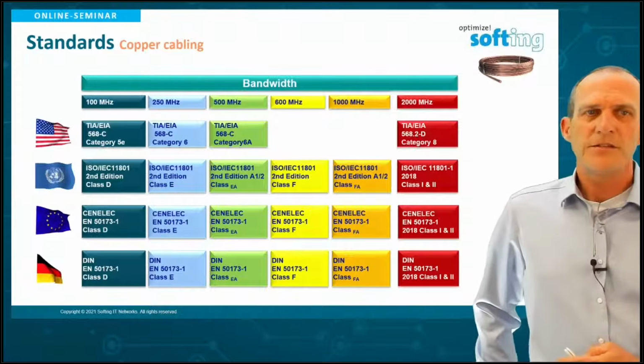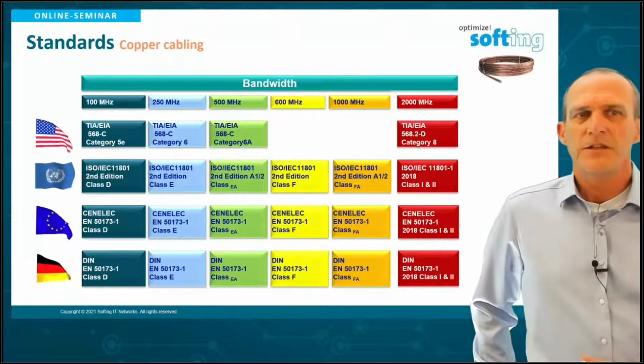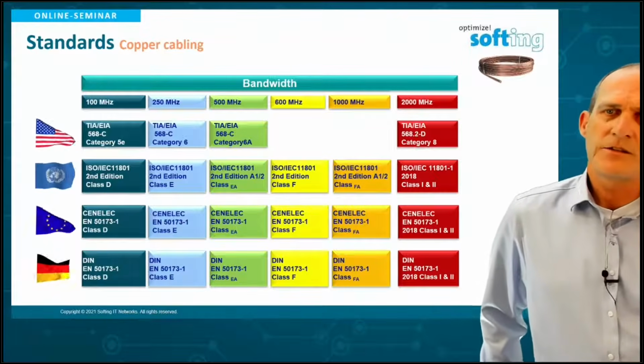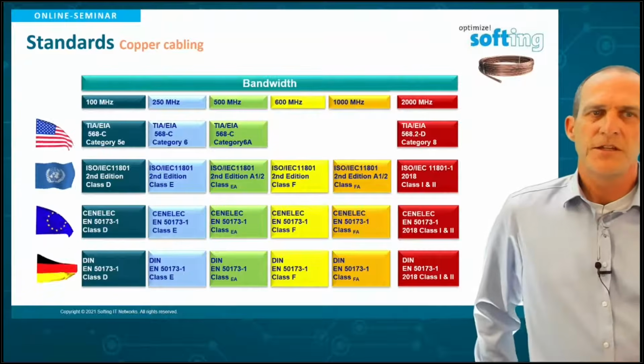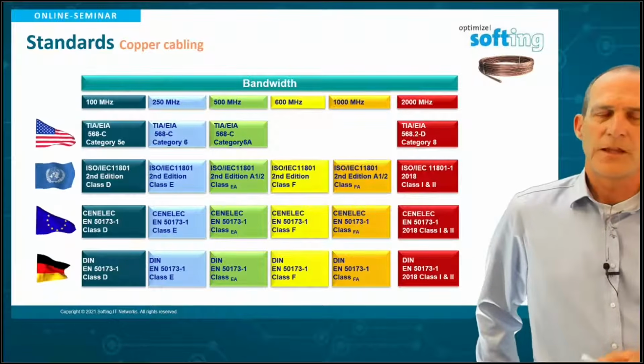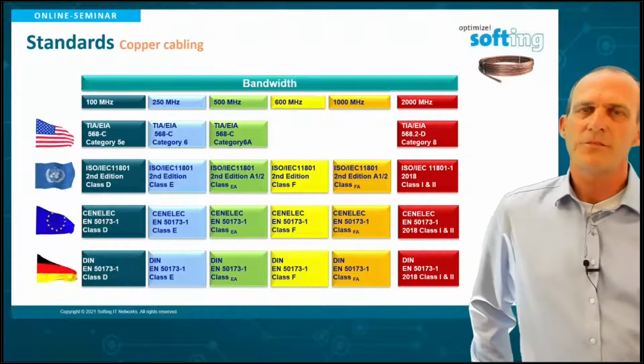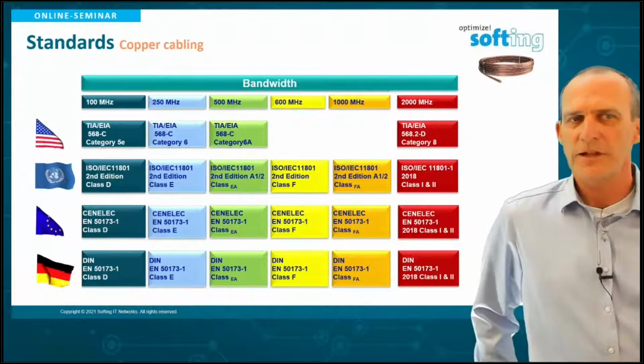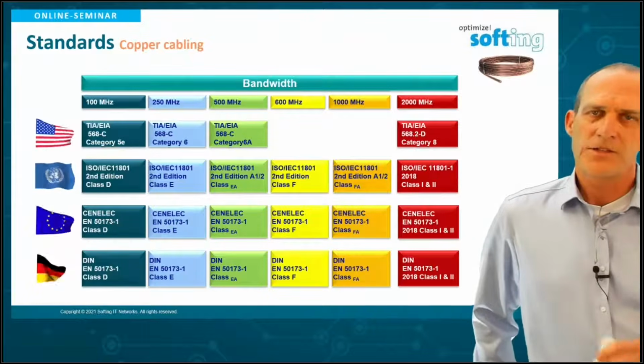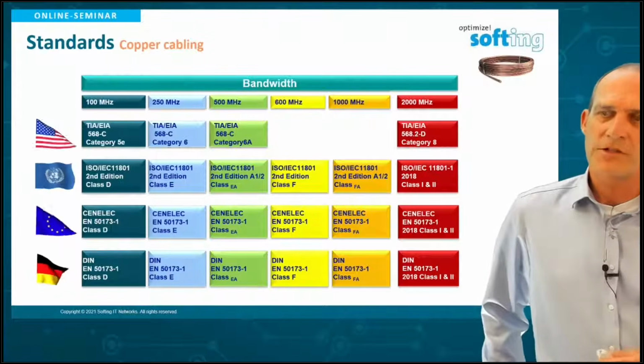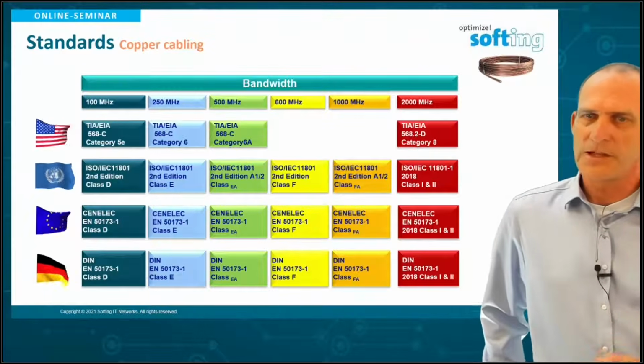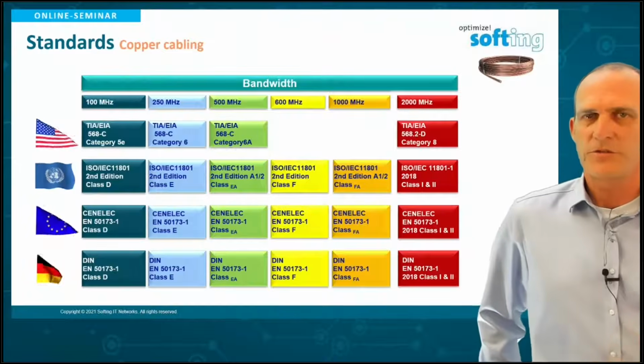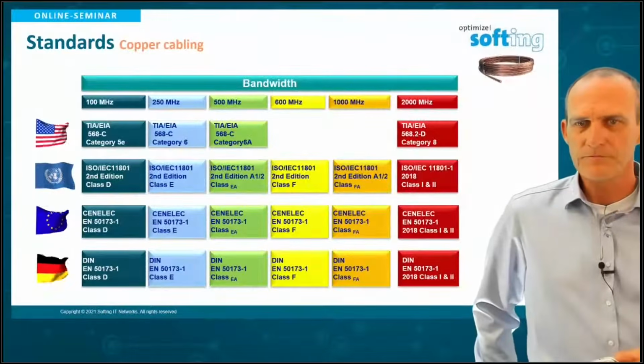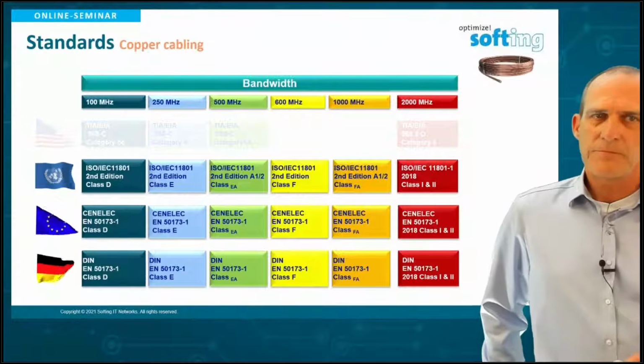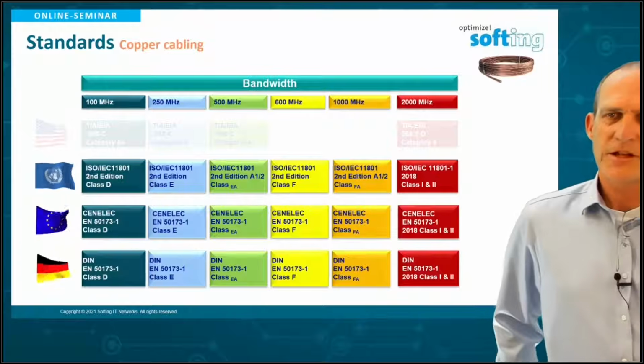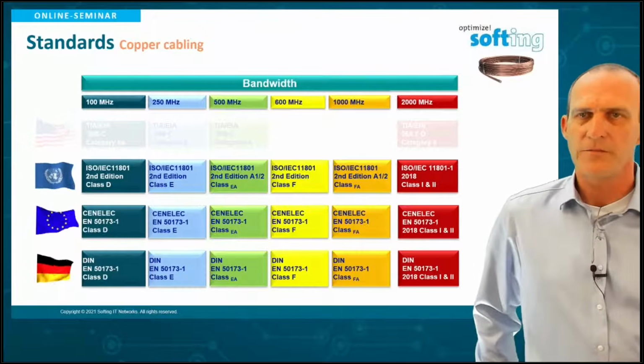After 2018, 2000 megahertz bandwidth was added: in TIA with category 8, and in the ISO and EN standards with class 1 and class 2 cabling. Class 1 cabling goes up to 2000 megahertz on RJ45 components, similar to TIA category 8. Class 2 cabling goes up to 2000 megahertz with non-RJ45 connectors, like Tera connectors, ARJ45 or GG45 connectors. So again, don't think too much about the American standards, leave them aside unless you really need them.